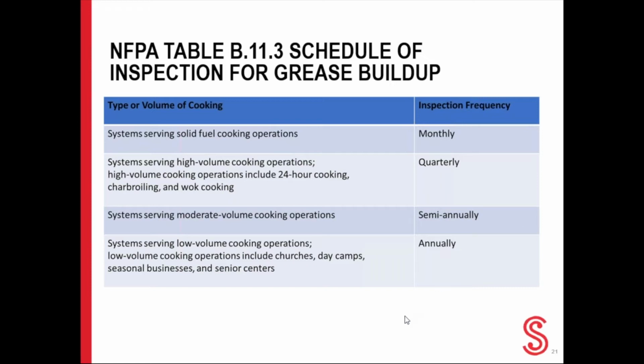The entire exhaust system, including vent piping, shall be inspected for grease buildup by a properly trained, qualified, and certified person acceptable to the authority having jurisdiction and in accordance with this table shown on the slide. If, upon inspection, the exhaust system is found to be contaminated with deposits from grease-laden vapors, the contaminated portions of the exhaust system shall be cleaned by a properly trained and qualified and certified person. A properly trained, qualified, and certified person is often interpreted to be a commercial exhaust system cleaning contractor who has knowledge of and the ability to comply with NFPA 96 standards.